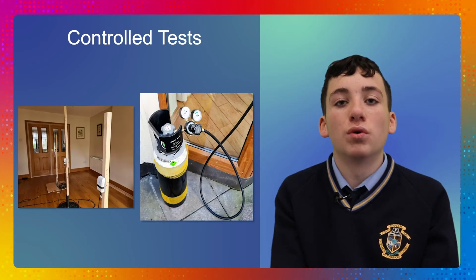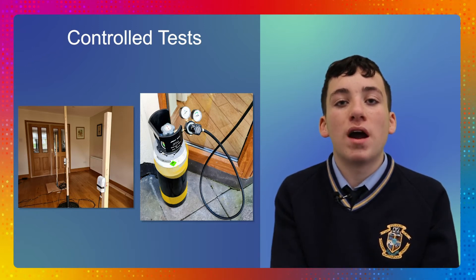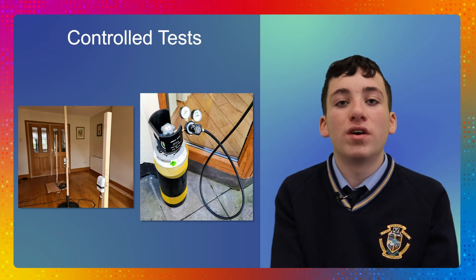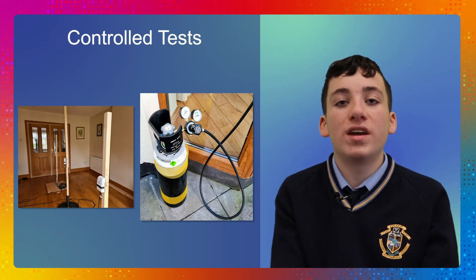At this stage, one of a range of ventilation measures was enacted and the decay of the CO2 was monitored. The air changes per hour rate, which is the true measure of ventilation that quantifies how many times per hour the air in the room is replaced by new air, was then calculated for each test automatically using a Python program.